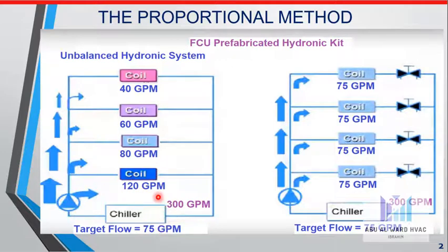The targeted flow for each coil shall be 75 GPM. But because it is an unbalanced system, near the circulator the nearest coil to the circulator will get 120 GPM.